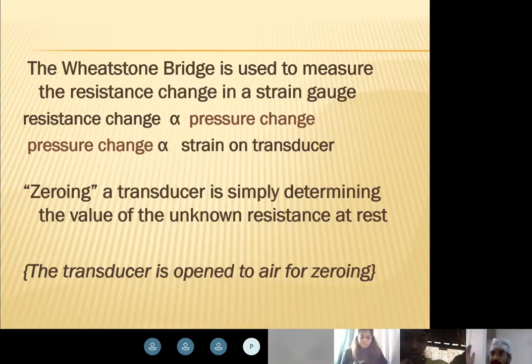So zeroing can be done before you even start inserting the catheter, before you start putting the central line, before you start putting the arterial line. To zero the transducer, it need not be placed at a certain level. It can be placed anywhere: on the ground, in your hand, inside the circuit itself, inside the cover. You can zero it wherever you want.